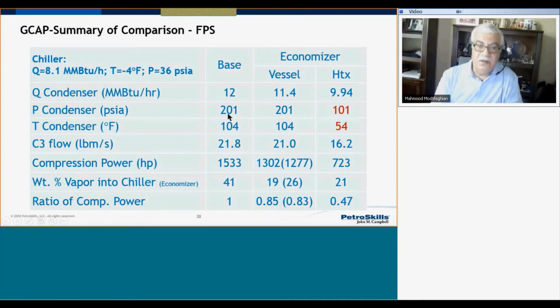The condenser pressure for the base case and the economizer with the vessel is the same because they both use the same condensing temperature. For the cooled process gas cooling media, the temperature was 54, so the pressure is 101 psi. Mass flow rate for the simple refrigeration system is 21.8. Here the mass flow rate is 21 through the second stage, but through the first stage the mass flow rate was 15.5 pound mass per second. The mass flow rate was the smallest in the last column, which was for cooled process gas.